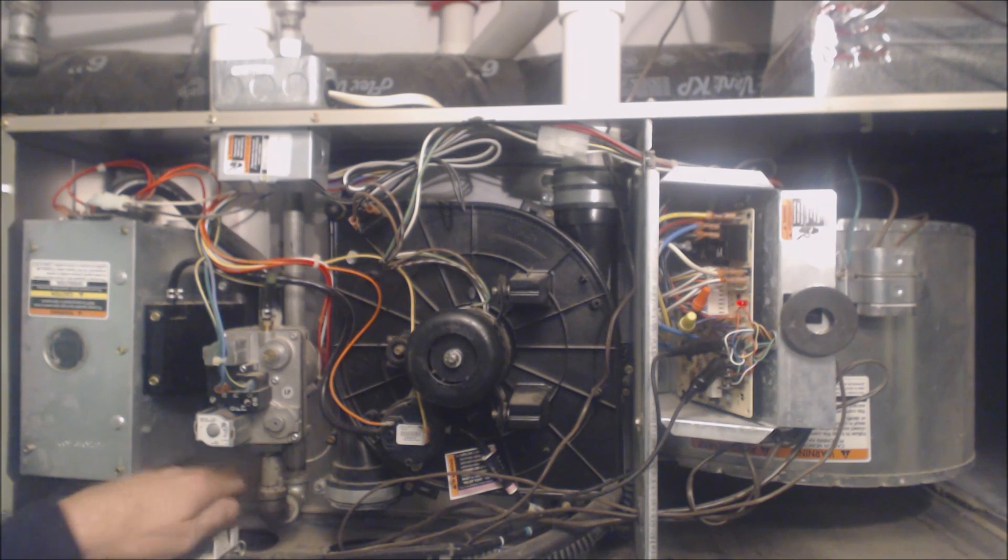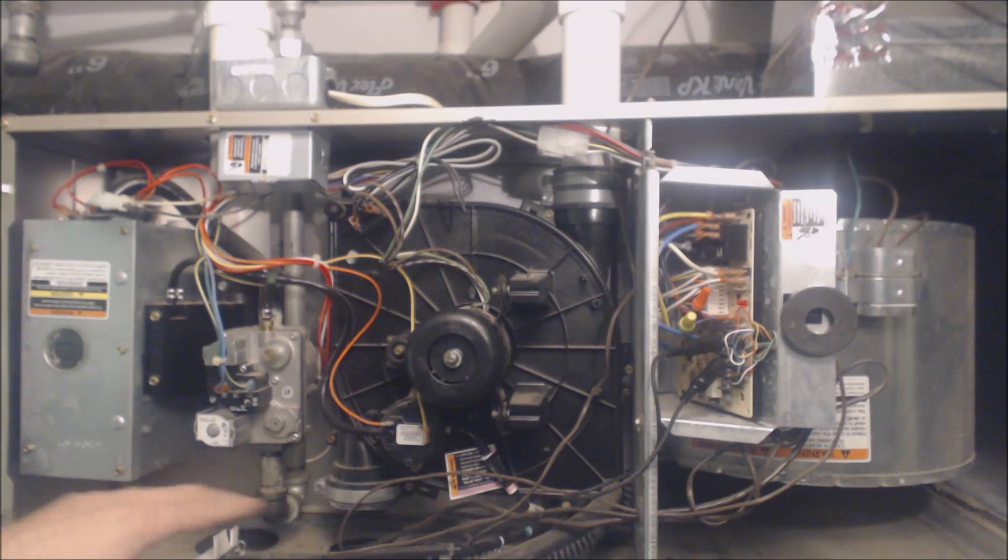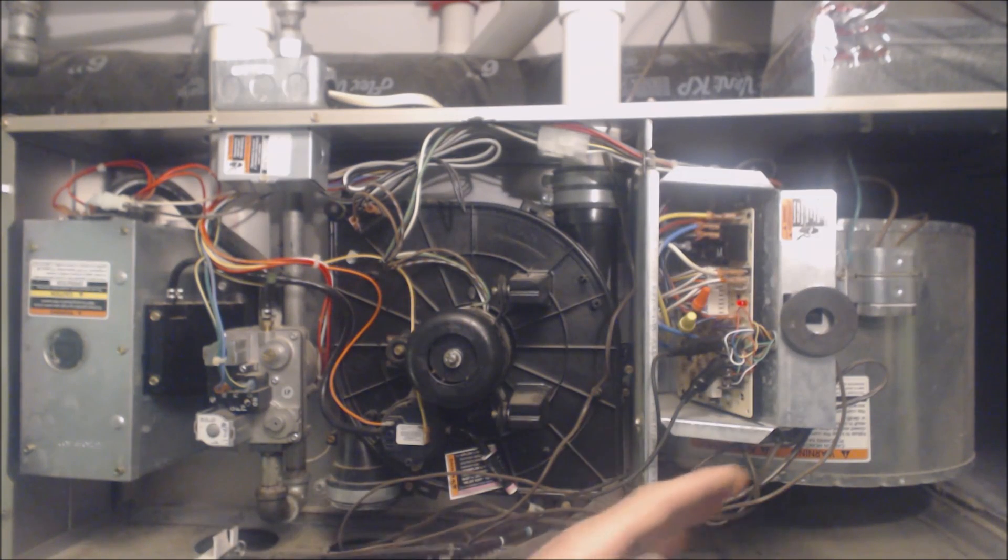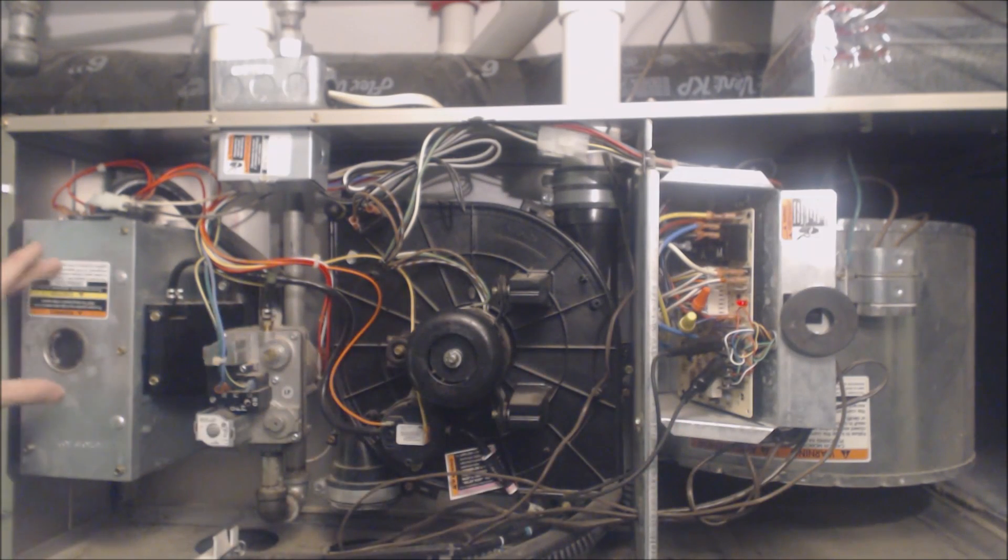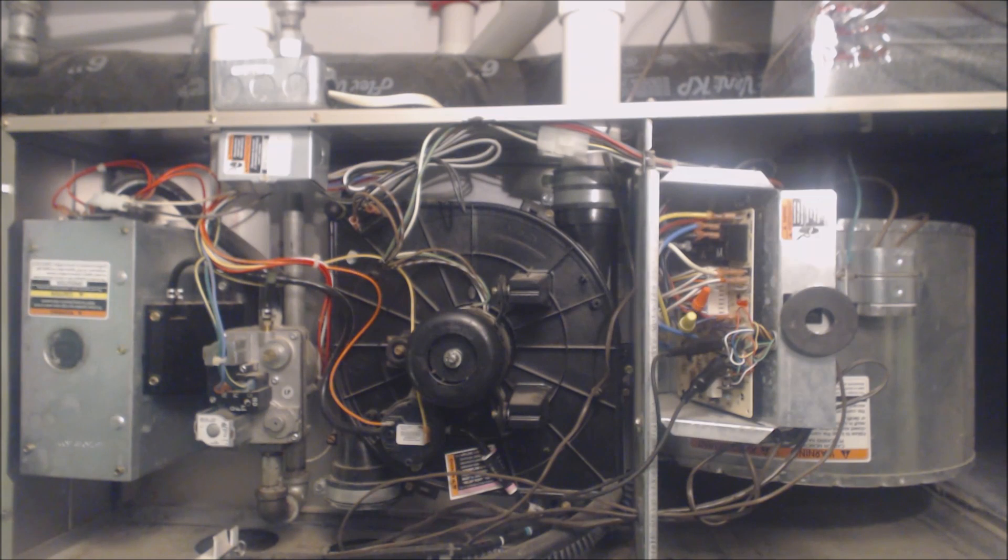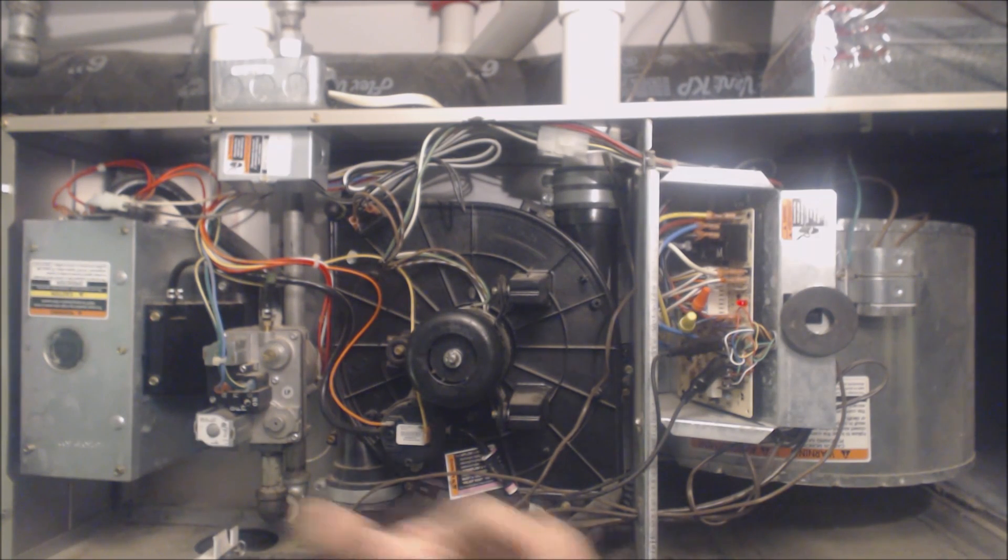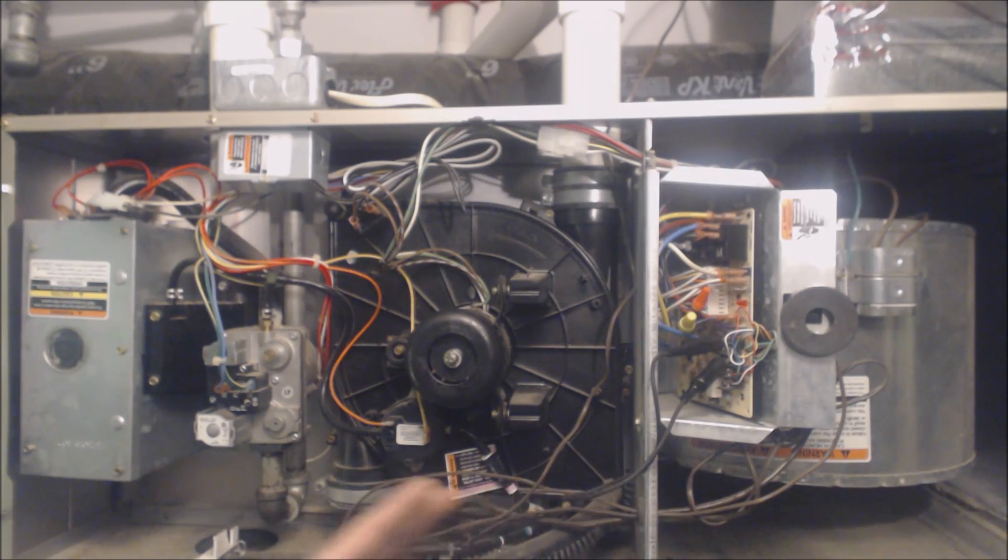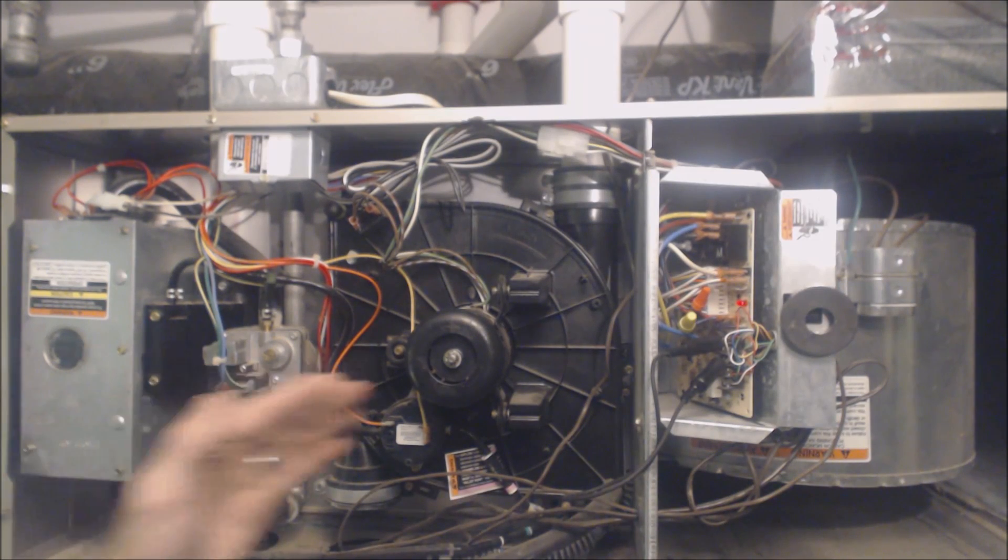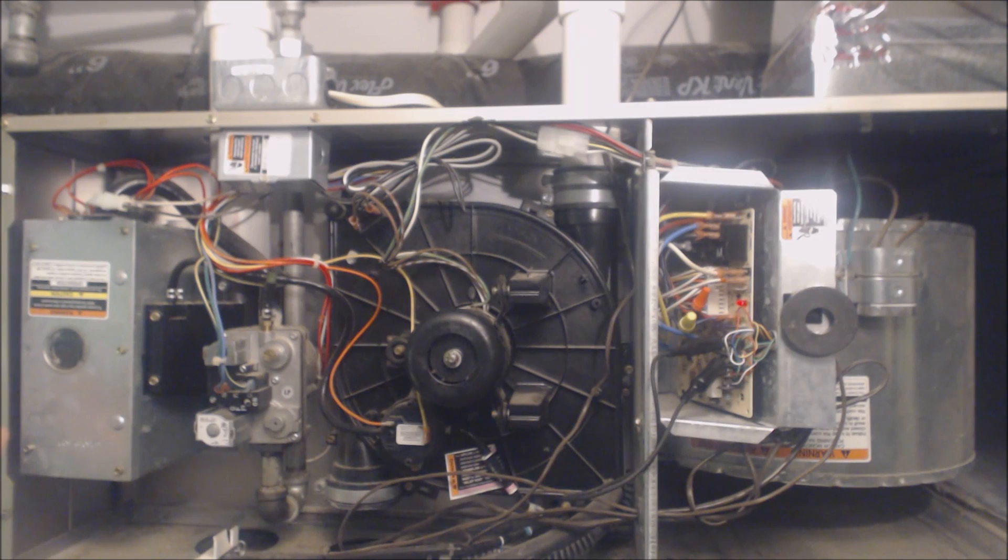The reason that the blower motor is going to run is to cool down the heat exchanger of the furnace because the furnace doesn't know how hot this is back here. So say it went through the sequence of operation and the burner box was heating up the heat exchanger but the blower motor never turned on yet. It wants to cool that whole heat exchanger down before starting the sequence of operation over again.